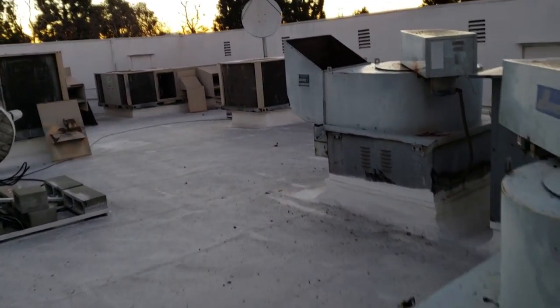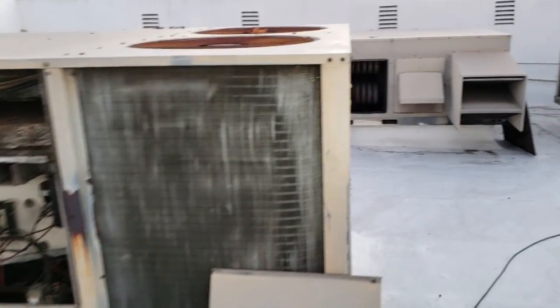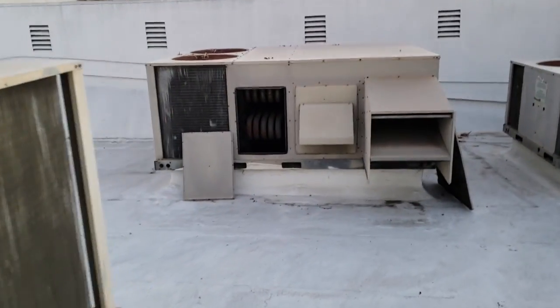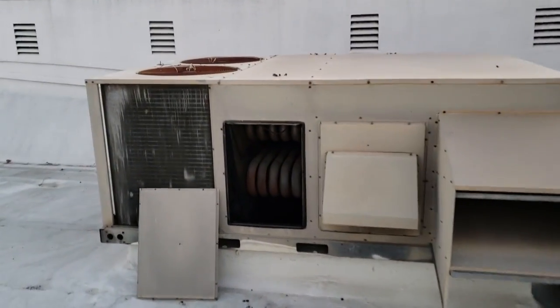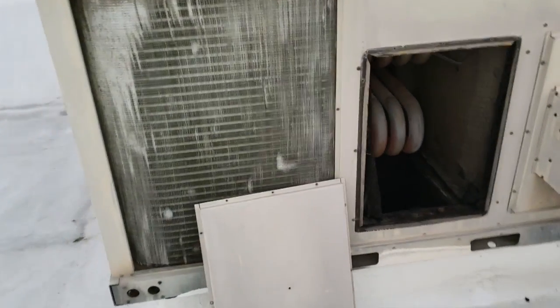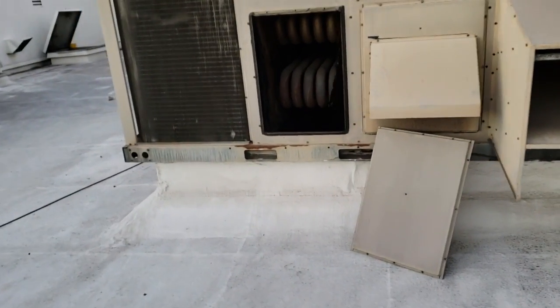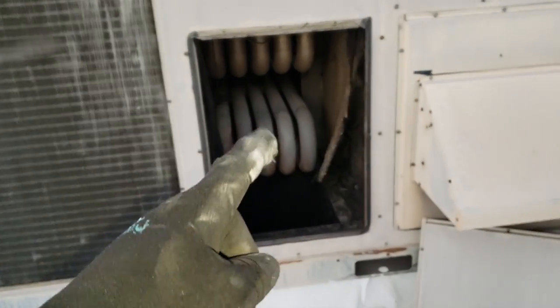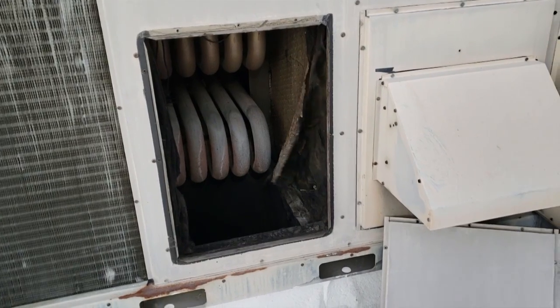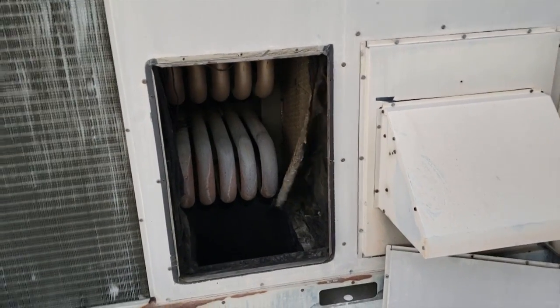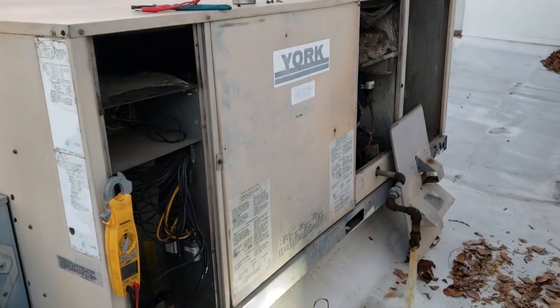What's strange though is I don't have a burning smell in this one, but I'm still going through my troubleshooting process. So I turned on all the exhaust fans and turned off both of the makeup air units, and I'm slowly turning the ACs on one by one, putting the building into a massive negative air pressure by shutting off the makeup air units, so that hopefully we can suck out some of this smoke smell, because it's pretty strong in these ACs. So I'm going to let this guy run for a bit. Definitely need to get that insulation cut off, because it's going to rub up against the heat exchanger, as it has been, and melt off. But we're just going through the troubleshooting.